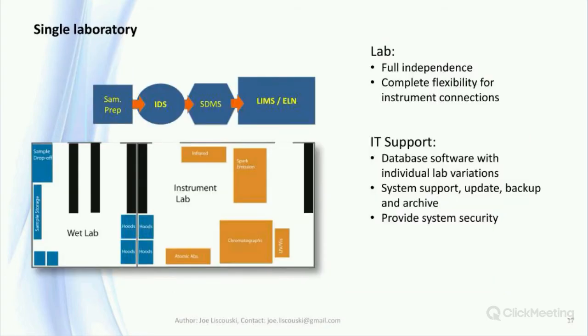In a simple situation — one lab, one system — the lab has complete flexibility in connecting instrumentation to the LIMS or ELN, as well as configuring the database to meet its needs. If specialized programming is needed to support an instrument, the lab has the freedom to do so. Commercial data systems have a library of software to support instrumentation. What happens if your device isn't supported? If it's a low-cost device it might be easier to replace it; if not, find something similar and modify the software. Instrument support requirements should be part of the user requirements; software modifications are an IT issue.